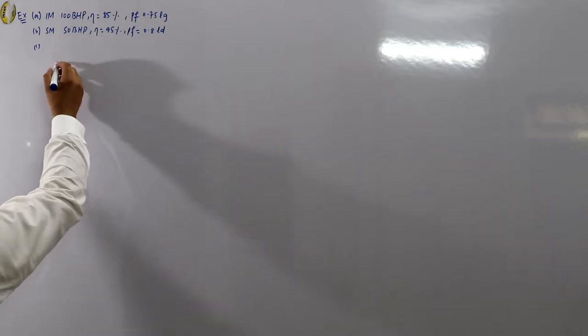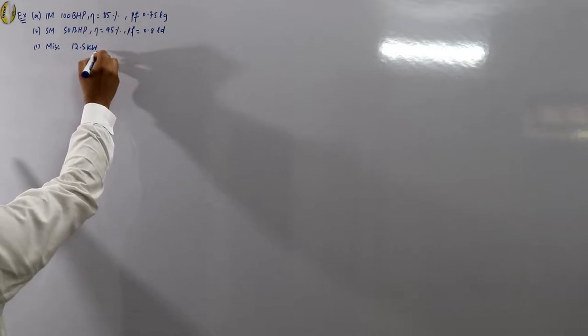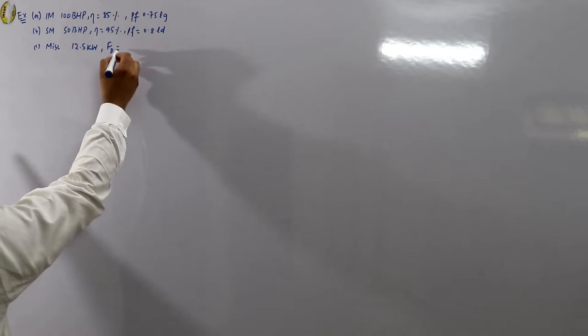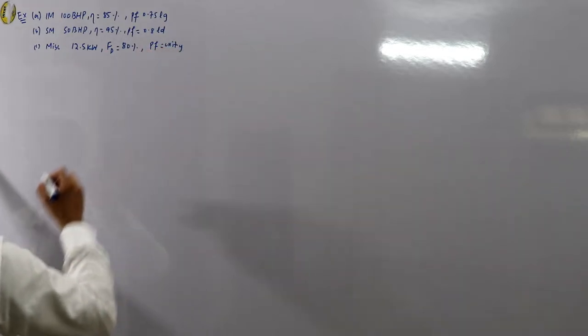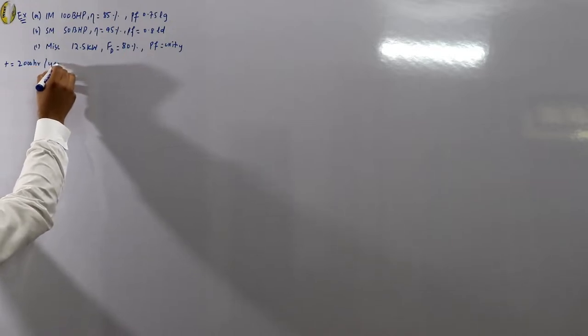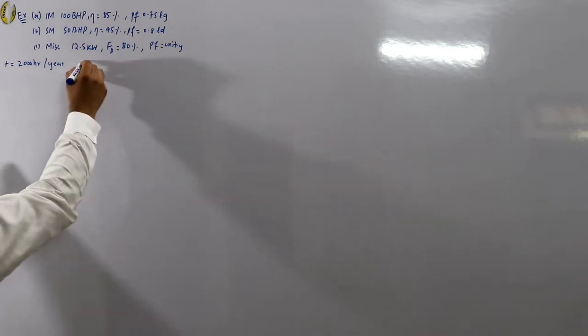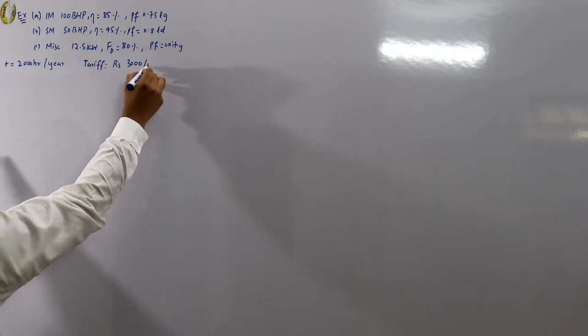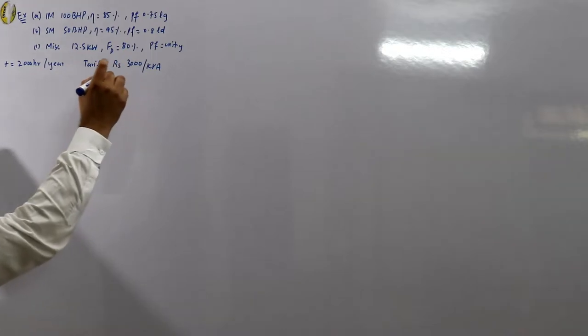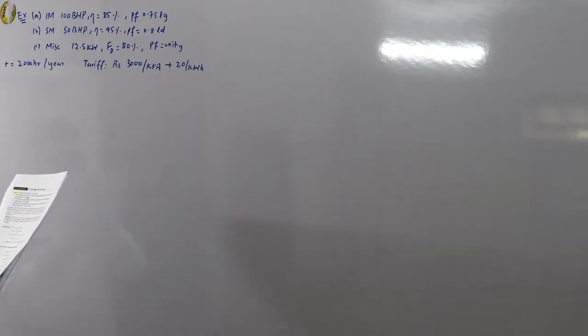Load C is a lighting and miscellaneous load amounting to 12.5 kilowatts, operated at a demand factor of 80%, and the power factor is of course unity. The factory works for 2000 hours per year and is charged with a two-part tariff: rupees 3000 per kVA of the maximum demand plus rupees 20 per kilowatt-hour.